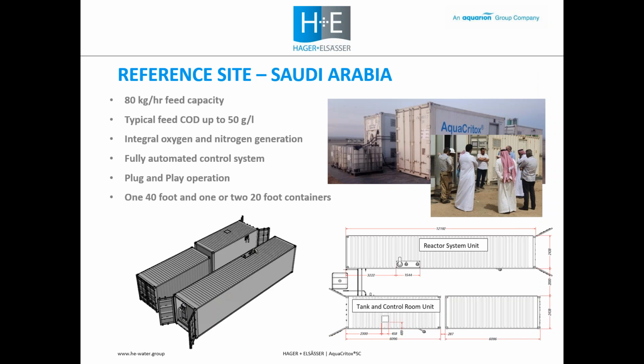So currently we have a unit operating in Saudi Arabia. This is an 80 kilo per hour unit with up to around 50 grams per litre maximum COD allowance at the feed. This package has an integral oxygen and nitrogen generation system. So within the very few modules that you can see in this picture, we are processing spent caustic. We are generating the utilities that we require for the process. And all we require here is a water connection and an electrical connection. And then this whole unit is plug and play.